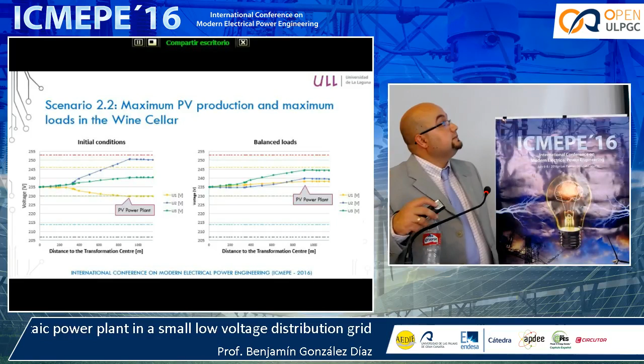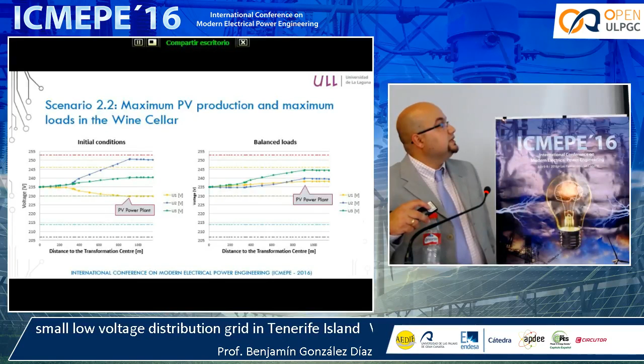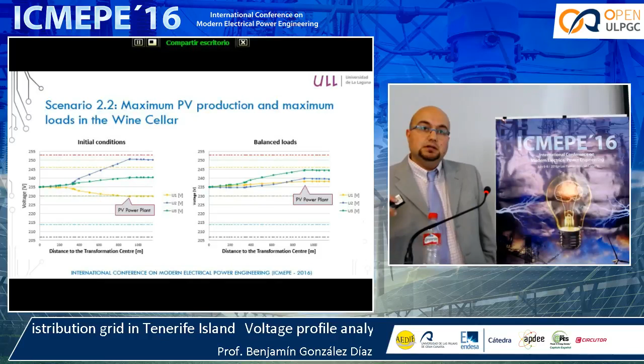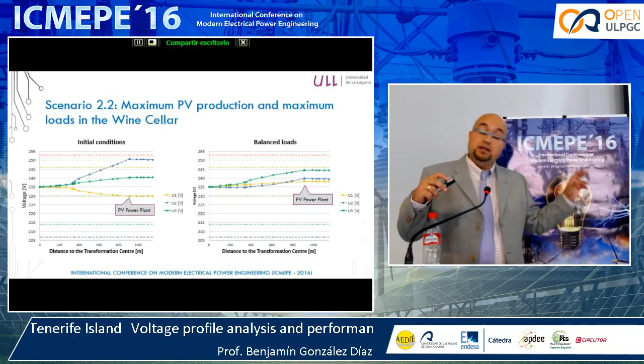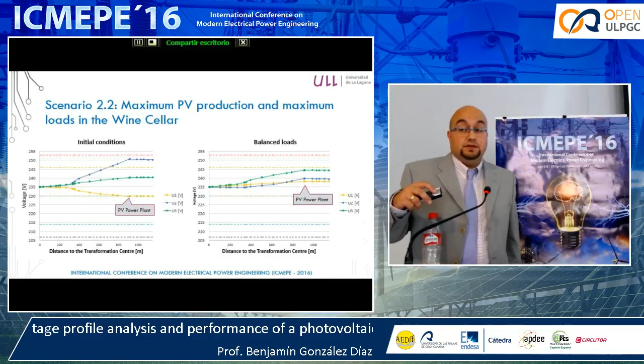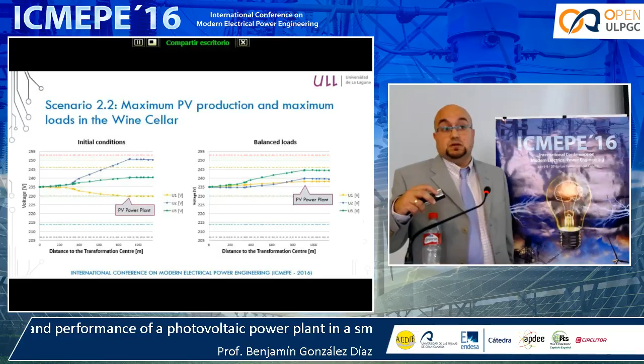Another case is maximum PV production and maximum load on the wine cellar. We can see that the voltage is so high. This simulation exactly reflects the actual case we had measured, because they are reaching more than 250 volts; the maximum was 254. This is so high above the upper limit.